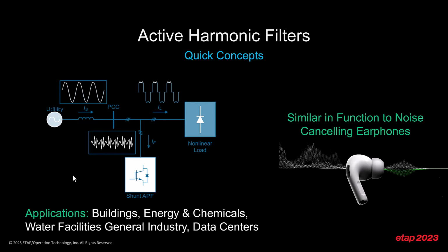Very similar to noise cancelling earphones, the closed loop control system therefore measures the line current for each harmonic and reactive power component, compares this with an internal target that is set by the customer, and then any deviation is injected and automatically eliminated. The selection capability of the individual harmonic components is usually a result of advanced control algorithms that are proprietary per vendor, and that's important to remember. And of course, there is typically a CT, or current transformer, that's used to sense the harmonic current, with the control loop usually left in open loop mode if the CT is on the load side, and in closed loop mode if the CT is on the network side. And this is important for adequate and correct harmonic cancellation.